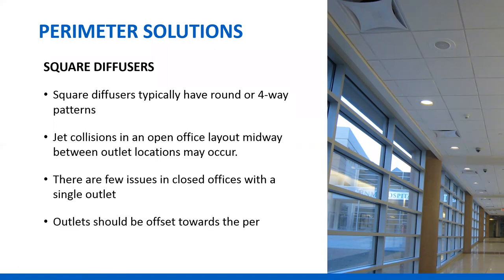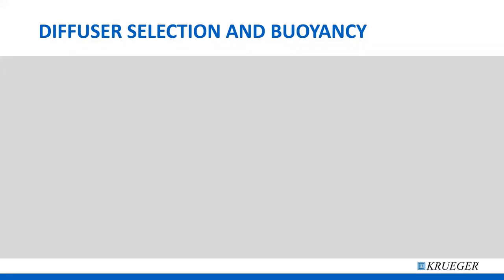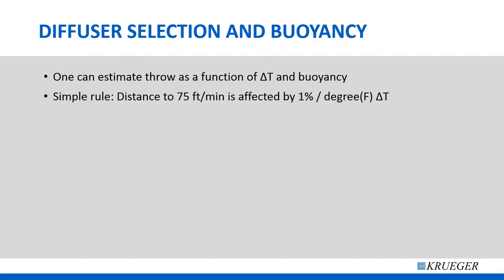Outlets should often be offset towards the perimeter. Buoyancy can be predicted with some degree of accuracy. We know that we can estimate the effect of temperature on throw using a simple equation, remembering that hot air rises and cold air falls. A simple rule: take the 75 feet-per-minute throw. Where do you get that? The catalogs print 50 and 100 feet-per-minute throw — 75 feet-per-minute will be in between the two. Almost every diffuser in the Krueger catalog has isothermal throw data, meaning room temperature.